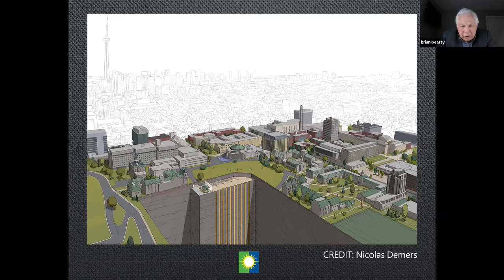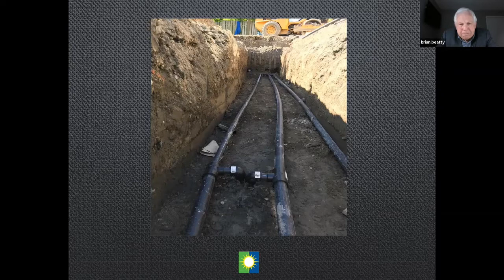This is what it looks like when you connect all those pipes, so all those boreholes. So you put a whole bunch of loops in a big field, and then you have to connect them all together with pipe. And this is where I mentioned at the outset, you use polyethylene pipe. Every joint that you see there is fused. That means it's melted together, and these are designed so there can be absolutely no leaks. And that's why we can afford to put these under buildings. Once they're installed and pressure tested, they will last more than the life of the building that's above it. It has a guaranteed lifetime of 50 years, but in reality, they will last 100 years or more. Next slide.